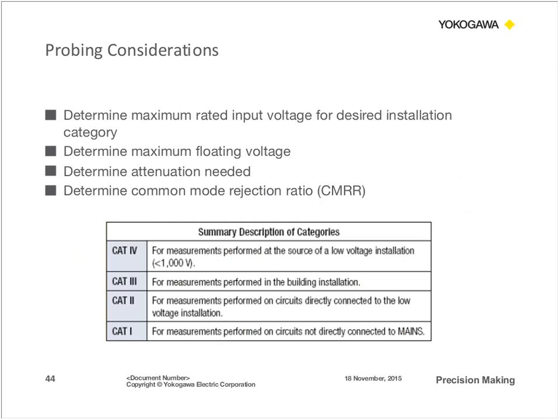Now, let's say you want to use differential probes. What do you need to consider when you're choosing differential probes? The first thing is considering the overvoltage category. IEC 61010 defines 4 different categories for voltage measuring devices. For example, category 4 is for when you're measuring across a source at a low voltage installation, so this is less than 1,000 volts. This is your power source. On the flip side, category 1 is when you're making benchtop circuit measurements that are not directly connected to a main power. So that's 120 volts or 240 or 480.